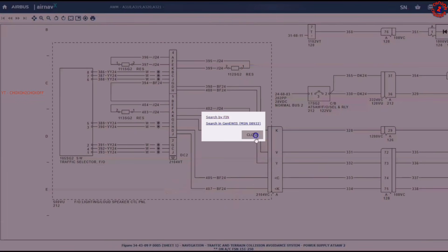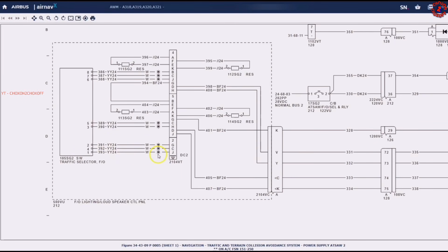You can see in the wiring diagram, all these wires are going in this terminal. This is a VT, okay, terminal block. So we have to install the contacts over here, the particular contacts, and then insert them in this VT. Before that, first we have to do extraction, and then we have to crimp it. The new wires will not come with the crimped pin, so we have to crimp it, and then insert it during installation.